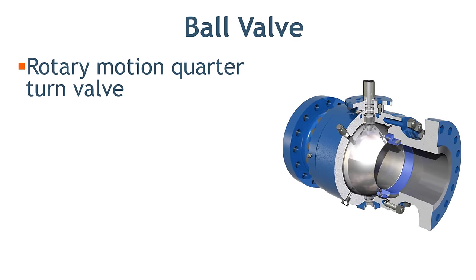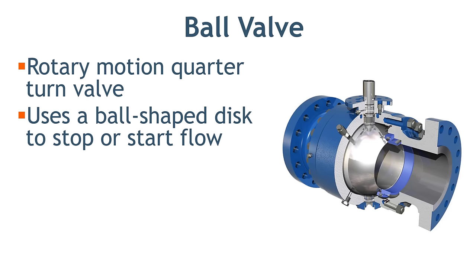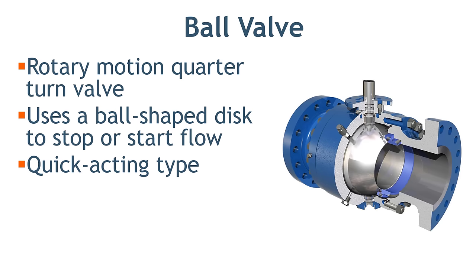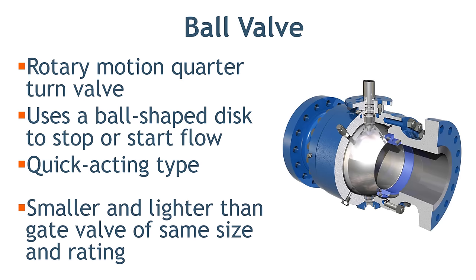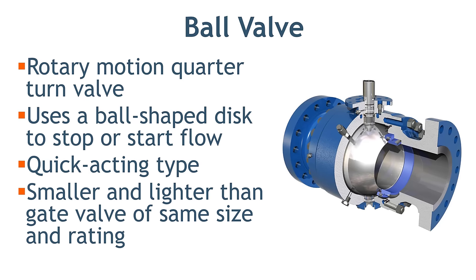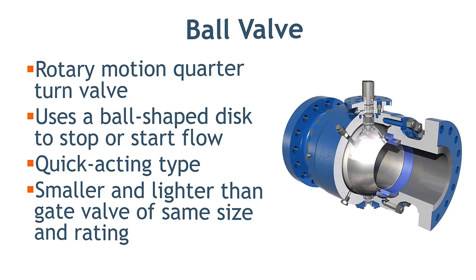A ball valve is a quarter-turn rotary motion valve that uses a ball-shaped disk to stop or start the flow. Most ball valves are of the quick-acting type which require a 90-degree turn of the valve handle to operate the valve. The ball valve is smaller and lighter than a gate valve of the same size and rating.